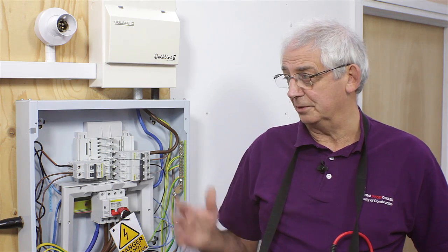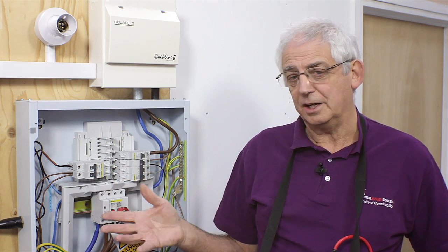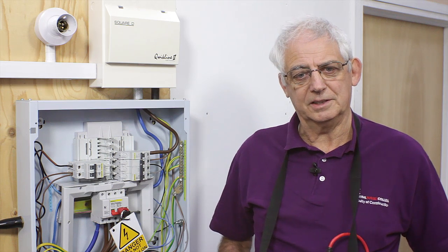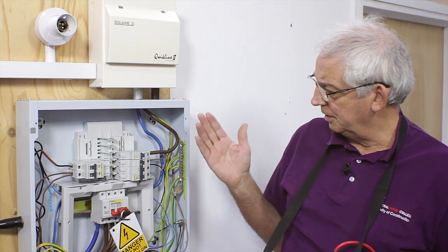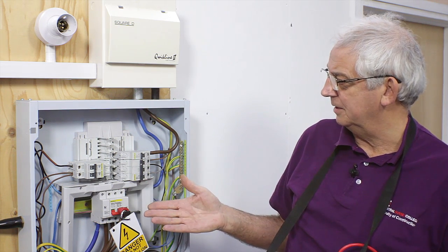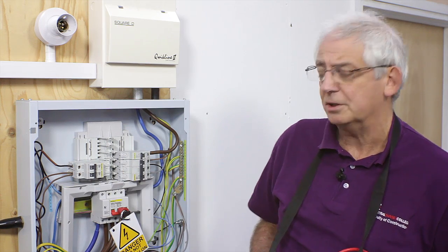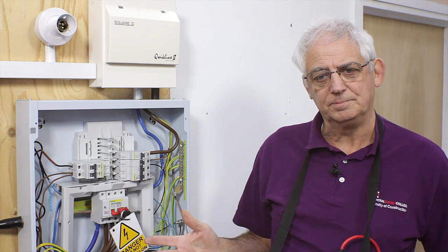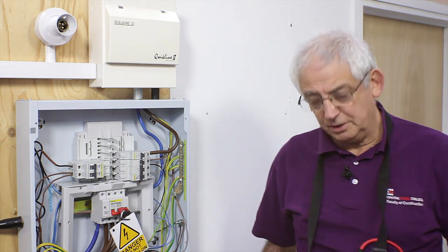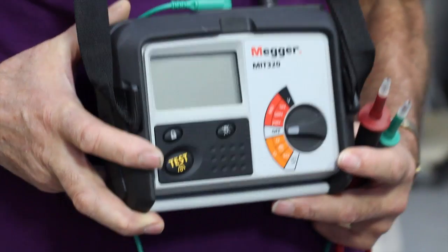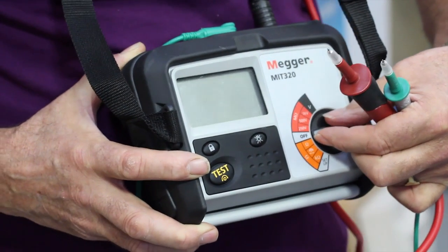So first part of the test, or the first part of the job, is to check that everything is disconnected as should be. As far as the board goes, the board is isolated, but we need to make sure that all of the circuit breakers are on because we're going to test the complete installation. We're going to use an insulation resistance tester, and we're going to use a test voltage of 500 volts.